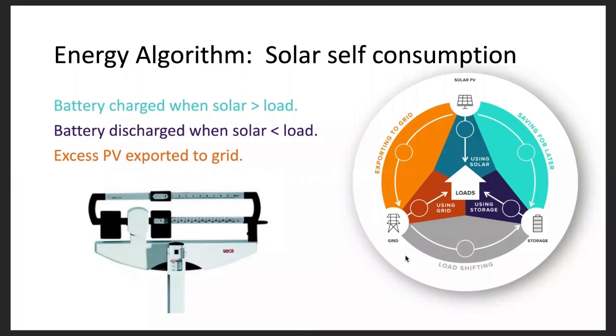In slightly more detail here, that energy algorithm for solar self-consumption: the battery is told to charge whenever solar is greater than loads, and the battery is told to discharge whenever solar is less than loads. Any excess PV is exported to the grid. It's pretty simple, and probably not new to most of you. And as far as net zero is concerned, that's our basic assumption, that we're trying to maintain net zero at the meter and provide the most value to the customer, especially when they're using time of use rates with the utility, where they can produce power during the day and use it when rates are higher during peak load time at night.